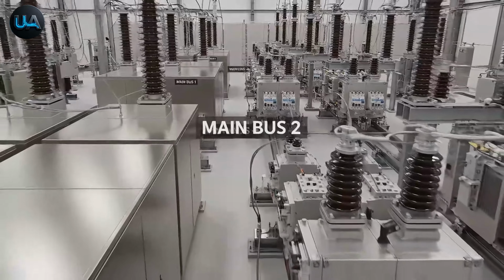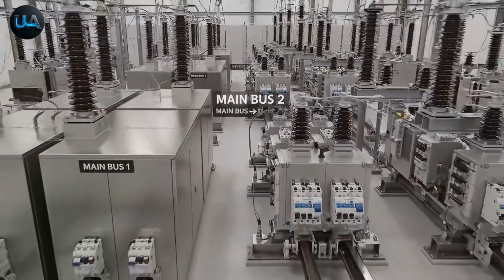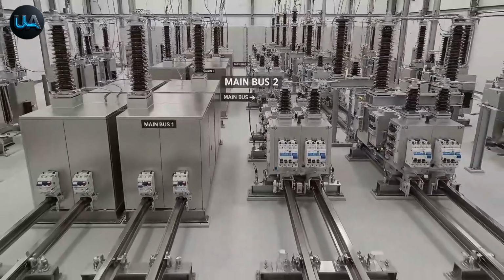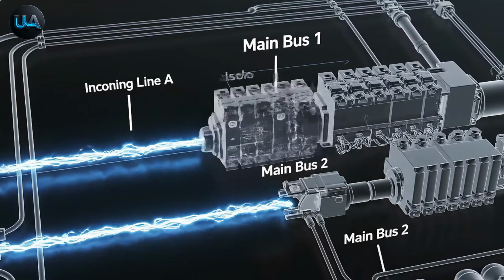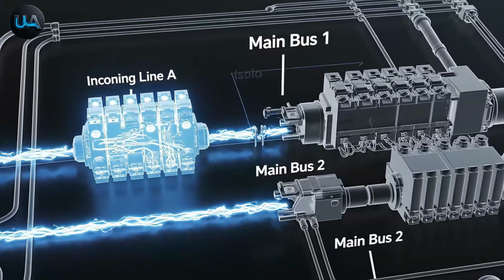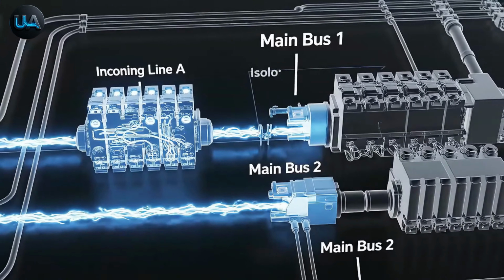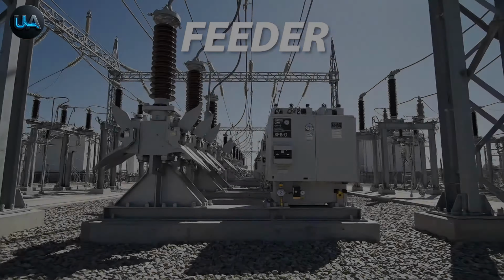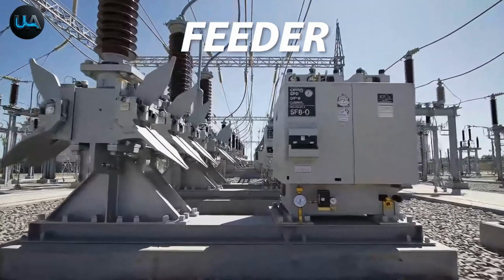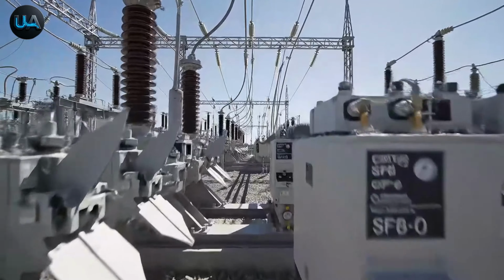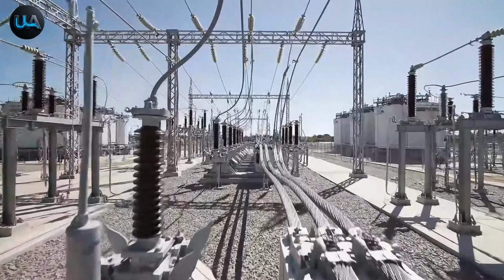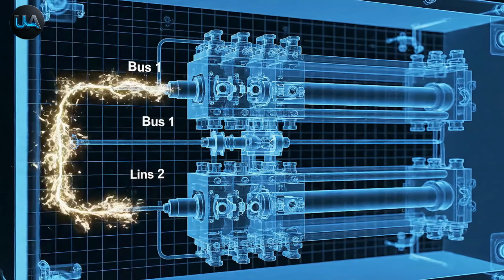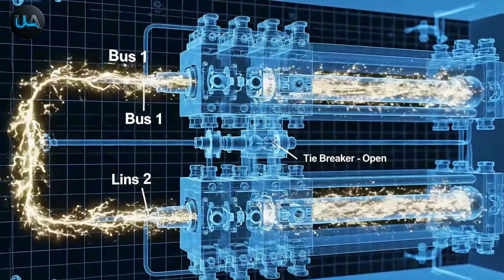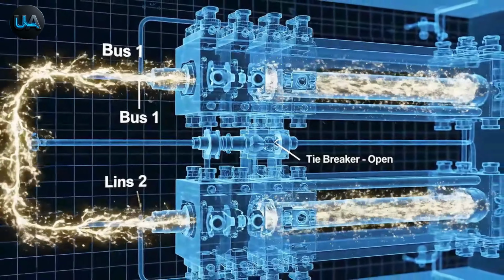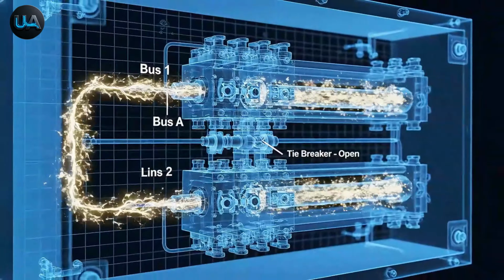A substation usually has two main bus bars, main bus 1 and main bus 2, for reliability. From the bus bar, the feeder lines utilize these isolators and the circuit breaker to transmit power throughout the network. Often, line A will feed bus 1 and line B will feed bus 2, and the two systems run independently.